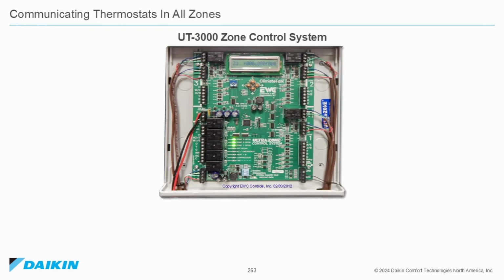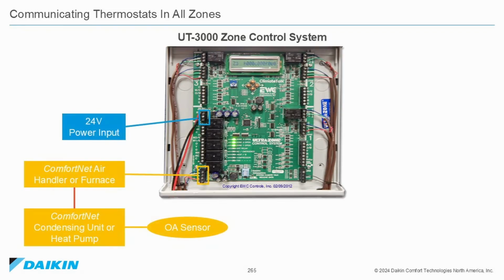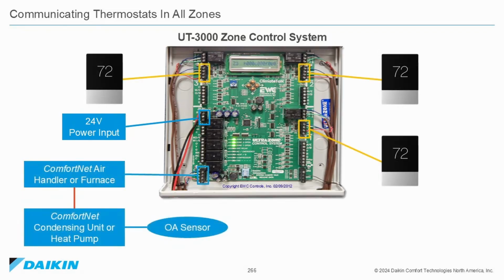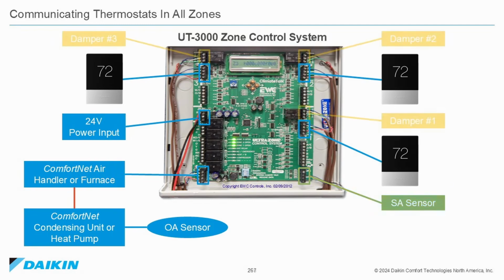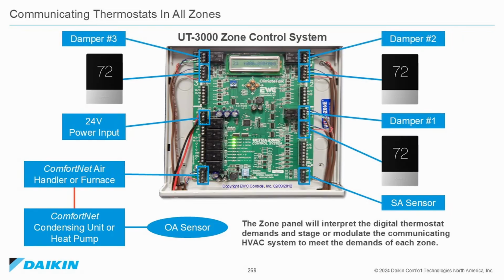Connection points using communicating thermostats in all zones on the UT3000 zone control system: the 24-volt power input, ComfortNet air handler or furnace, ComfortNet condensing unit or heat pump with the outdoor air sensor, the 3 thermostats, supply air sensor, and damper 1, 2, and 3 connections. The zone panel will interpret the digital thermostat demands and stage or modulate the communicating HVAC system to meet the demands of each zone.